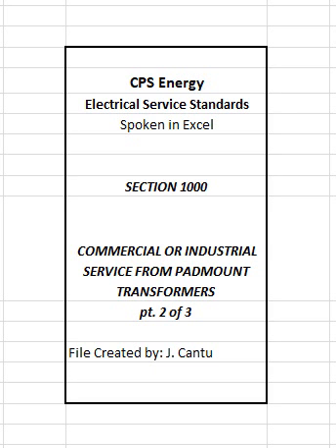13. Tap box shall be permanently and legibly marked with the voltage and current rating for which they are designed, and with the manufacturer's name or trademark in such a manner as to withstand the conditions. Such marking shall be located inside on the left side panel near the front of tap box. 14. Tap box shall also be equipped with continuous hinge or 3-barrel hinge cover double doors with stainless steel hinge pins. Door shall be secured by a 3-point locking mechanism and a T-handle with provisions for padlocks. 15. The tap box shall be equipped with padlock hasps for CPS Energy locks and 2 each pentabolt locking devices located at top and bottom of door assembly properly securing both doors.